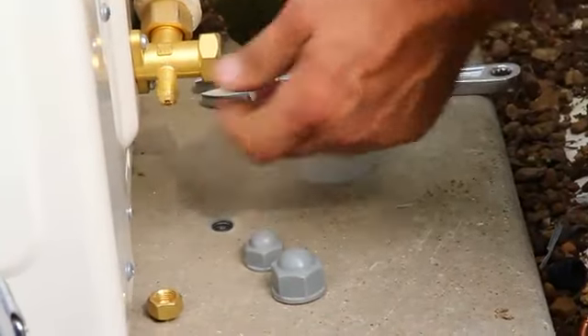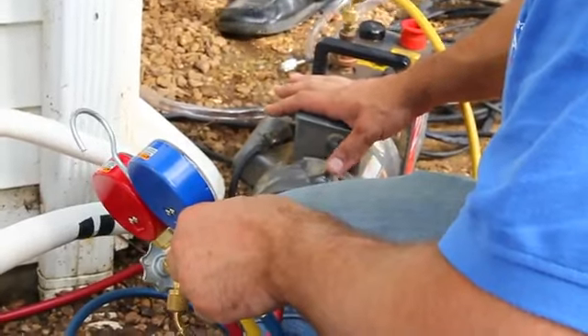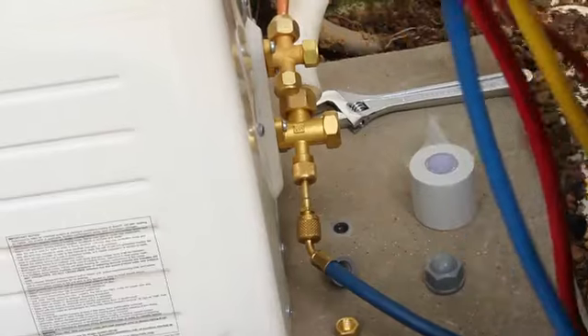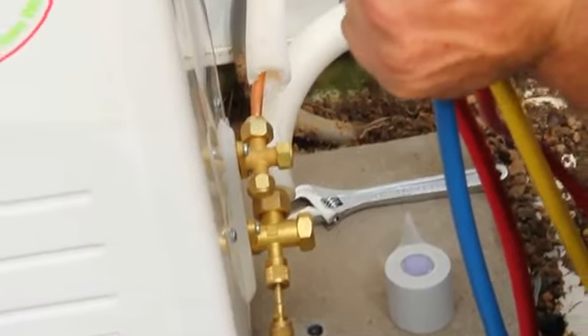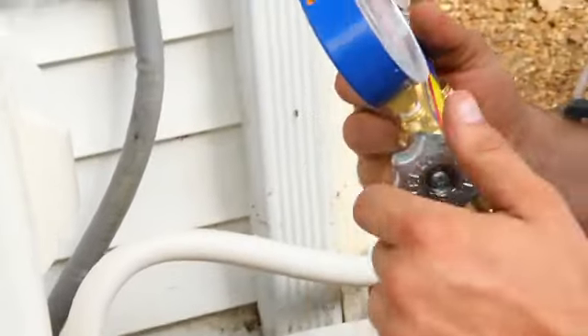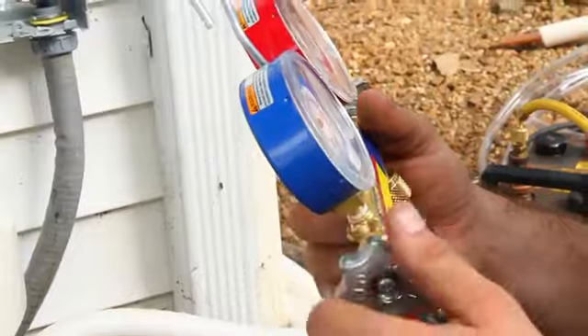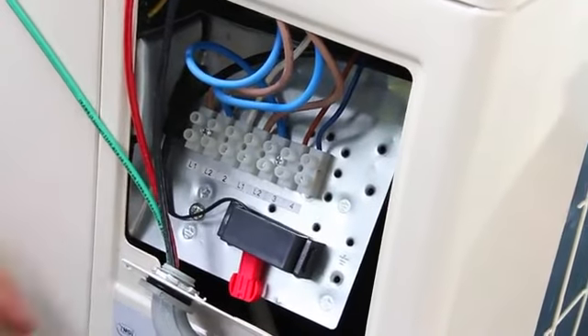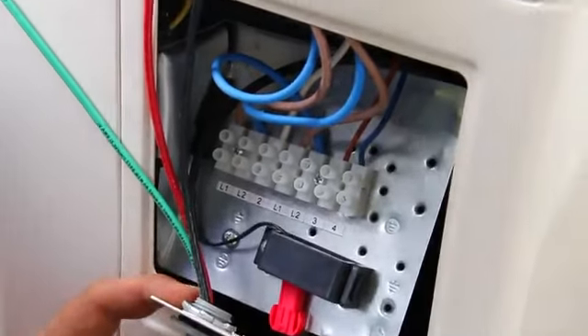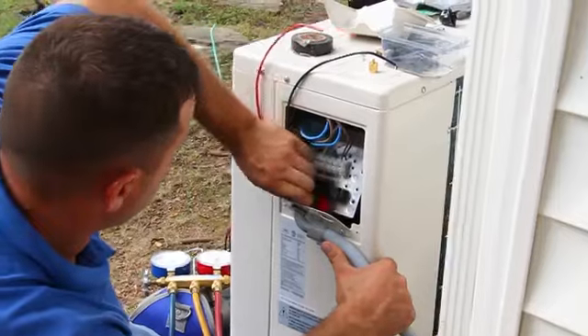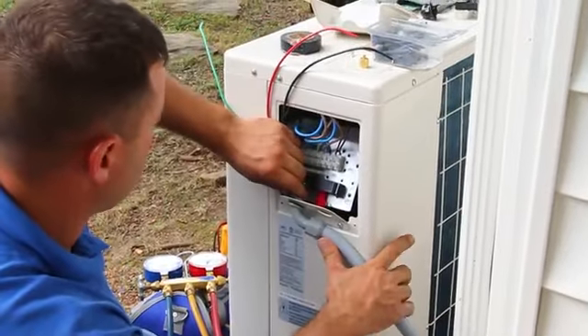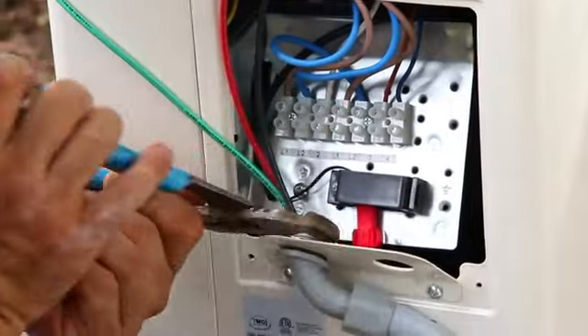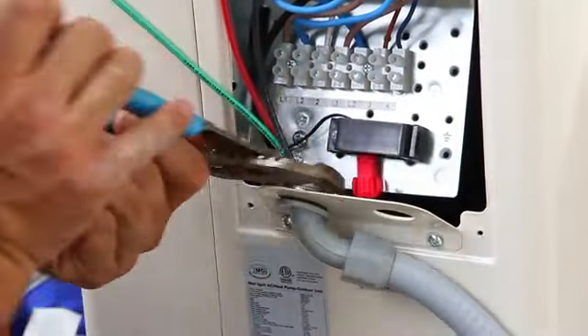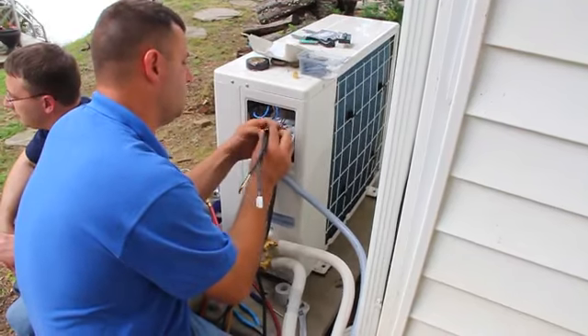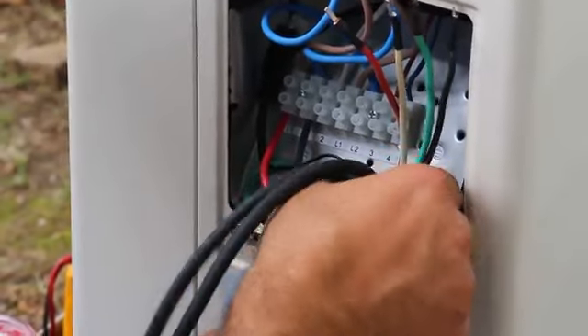With that accomplished, it is time to prepare for a future leak check on the system. You will pressurize the system, usually with nitrogen, according to installation specifications, and then wire the unit before performing the final leak check. Before you do any wiring, make sure the power is off. This cannot be stressed enough. Remove the cover on the outdoor unit for electrical wiring and set it to the side along with the screws, since we will be replacing the cover once we are done.